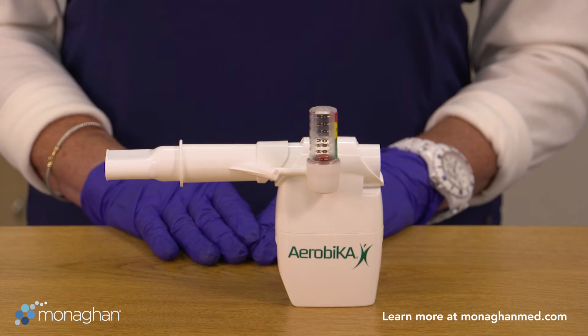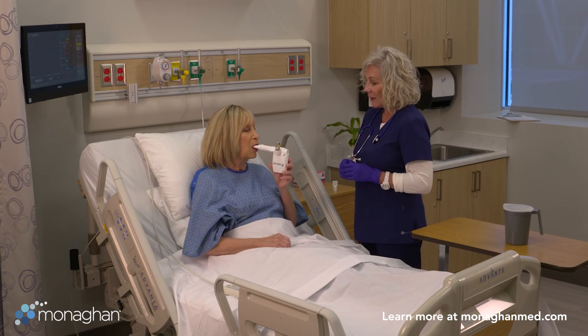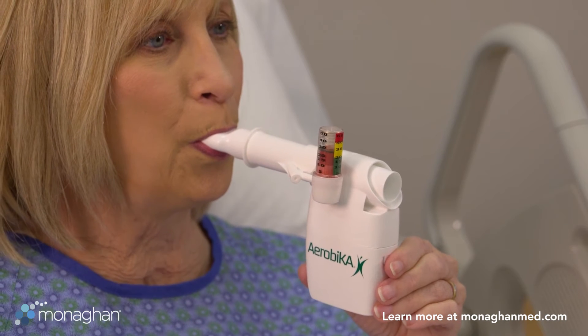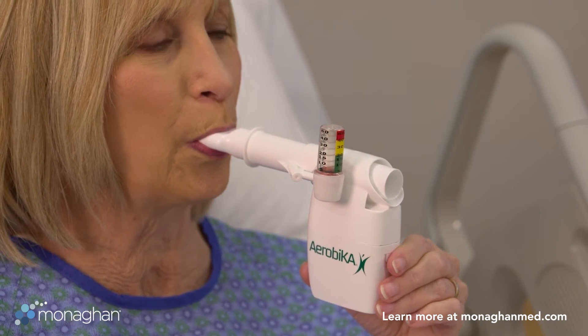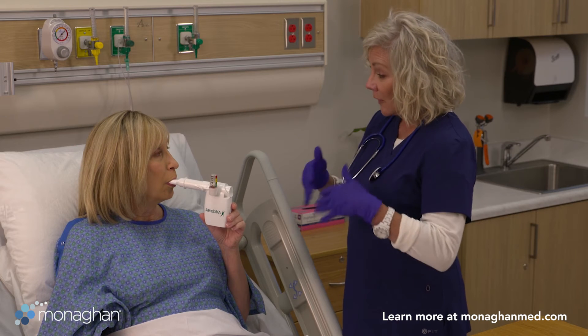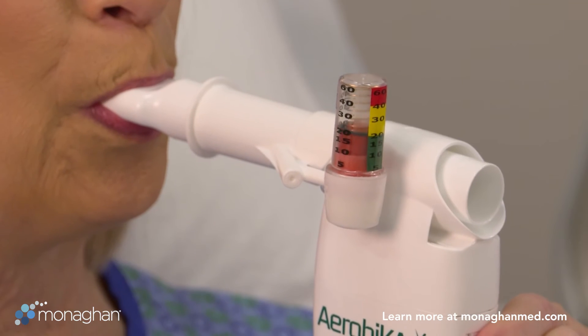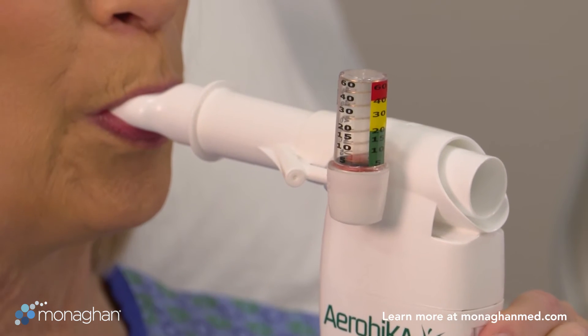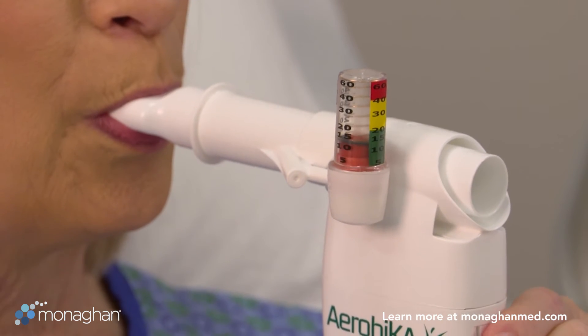The Aerobika OPEP device with manometer accessory offers added benefits to both clinicians and patients in helping determine proper resistance settings and monitoring exhalation technique to maximize treatment effectiveness. The red, yellow, and green zones allow for quick recognition if pressures move out of the therapeutic range so adjustments can be made.